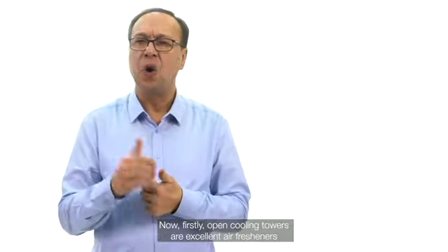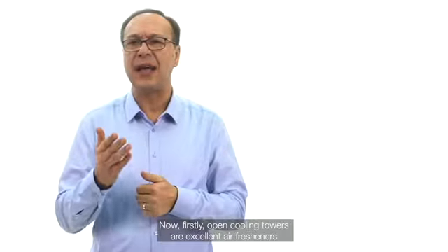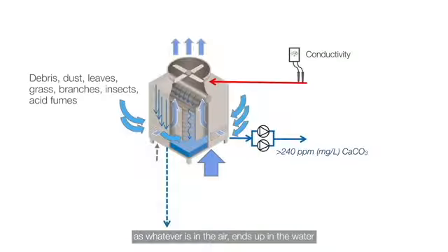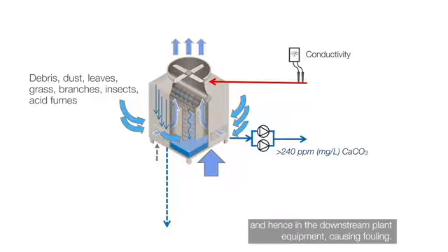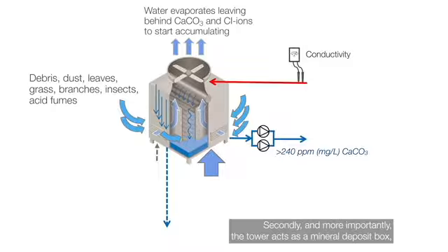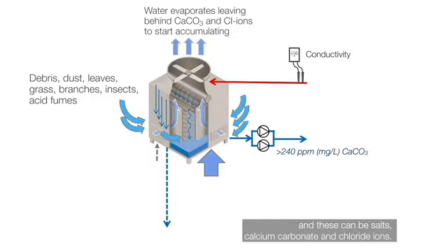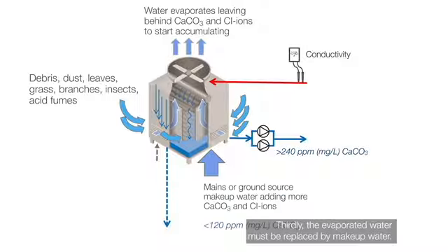Now, firstly, open cooling towers are excellent air fresheners, as whatever is in the air ends up in the water, and hence in the downstream plant equipment, causing fouling. Secondly, and more importantly, the tower acts as a mineral deposit box, with the water evaporating, leaving behind the unwanted minerals, and these can be salts, calcium carbonate, and chloride ions. Thirdly, evaporated water must be replaced by makeup water, and this brings even more unwanted minerals to the recirculating water.